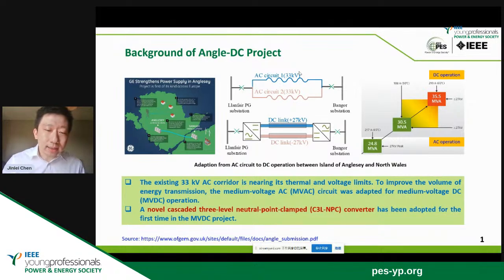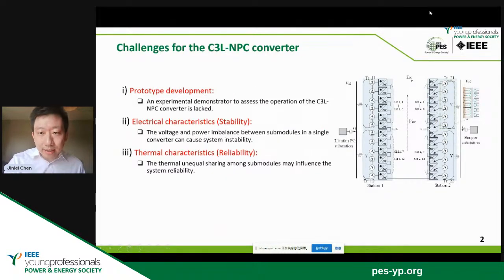And in this system, a novel cascaded three-level NPC converter has been adopted for the first time. As shown here, for this type of converter, there are 12 submodules cascaded together in each converter station. We can see that the DC sides of the submodules are connected in series, while the AC sides are in parallel connection using isolation transformers.